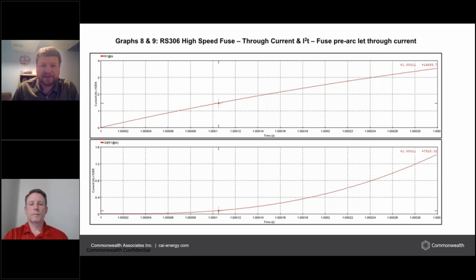So like Chris mentioned earlier in the presentation, DC systems are heavily based on site specifics. When you look at DC rise, it's controlled by the L over R of a circuit. LRC if you want to be specific, but there's much more inductance than capacitance generally in the DC systems of BESS applications. There is a capacitor on the inverter that we take into account, but generally it is dominated by the inductance of the system. And the inductance of the system comes from the cabling specifically.